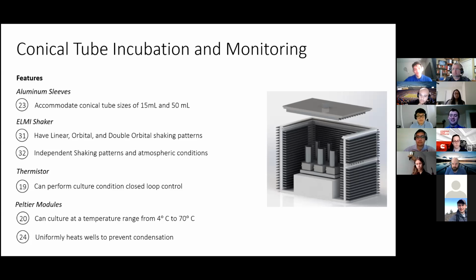Yes. So for the heat transfer, there has been extensive redoing of calculations for this. Not a lot of heat transfer actually goes to the inside fins for small incubation times, because it takes a long time for the heat to transfer over what is essentially, it's not a vacuum, of course, it's a gas, but slow gases. So unless you're incubating for a long period of time, most of the heat transfer out actually goes through the base, and then it goes to the outside through the outside fins. As far as maintaining temperature, it should not have a problem for the small incubation times.